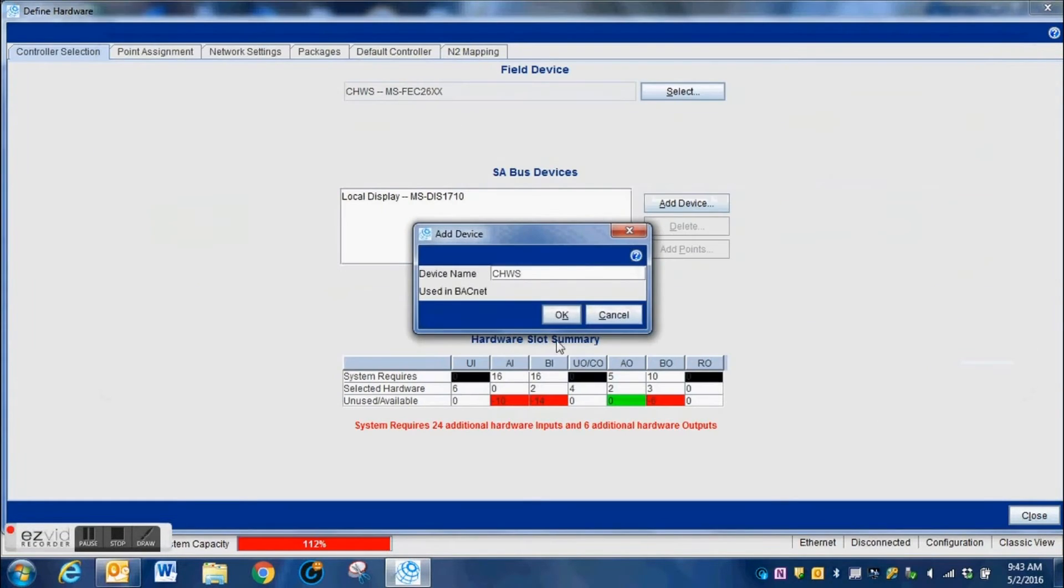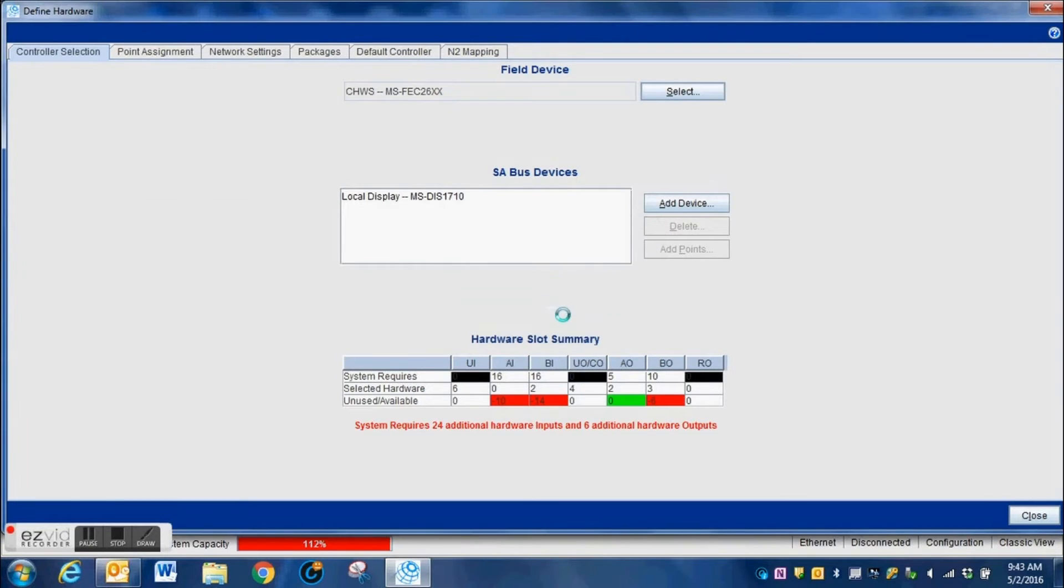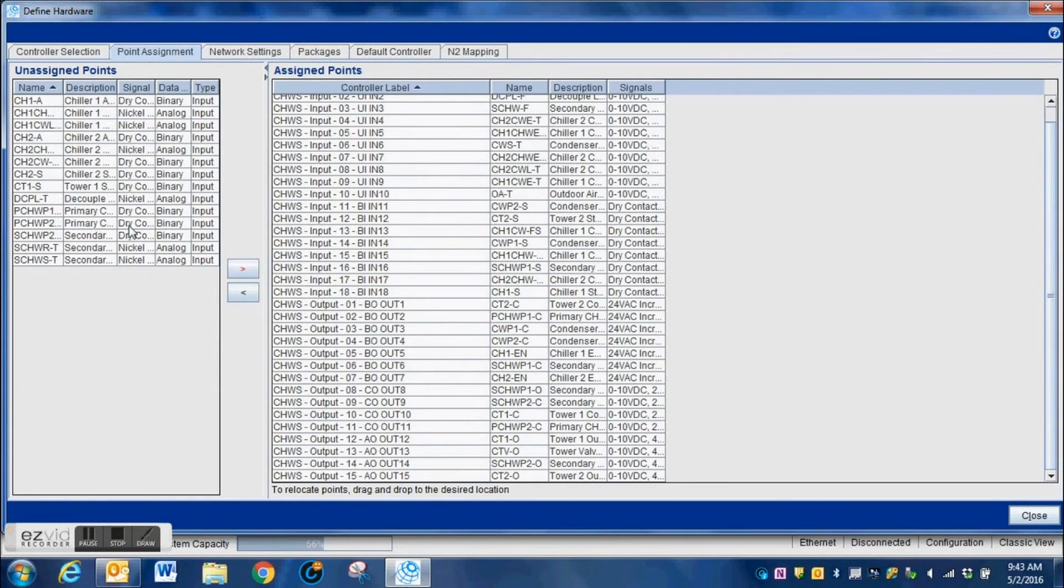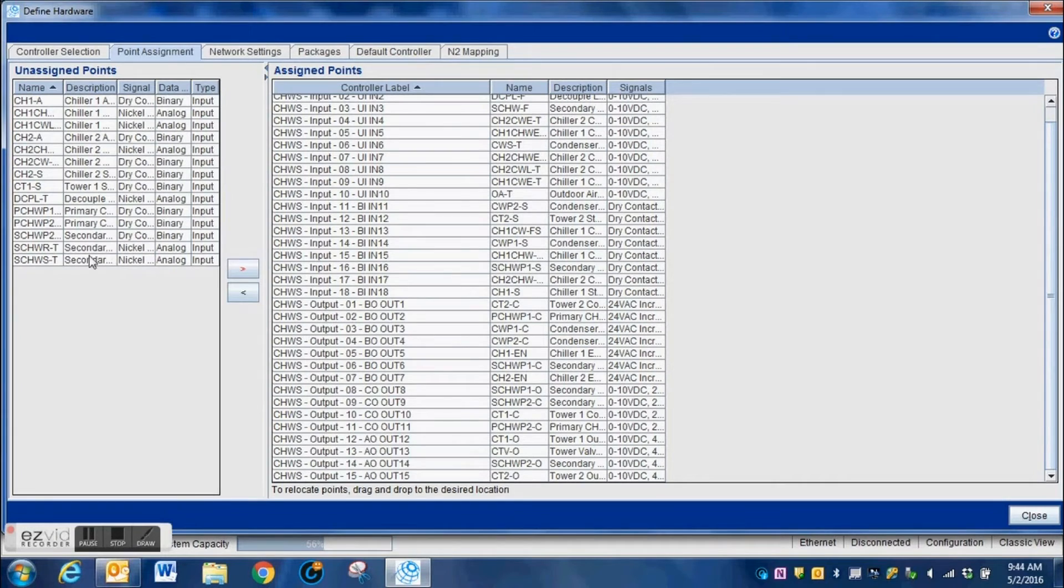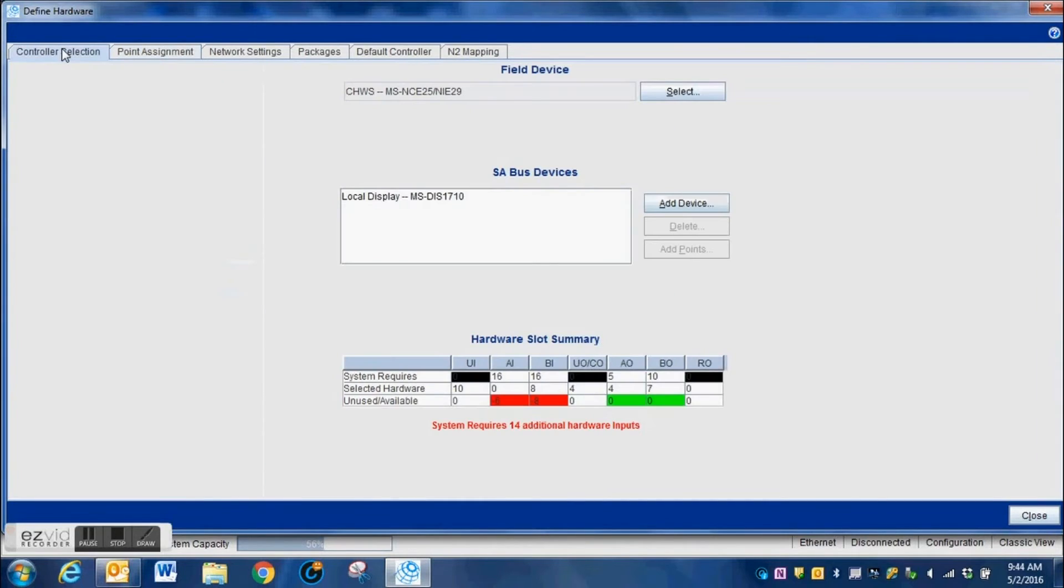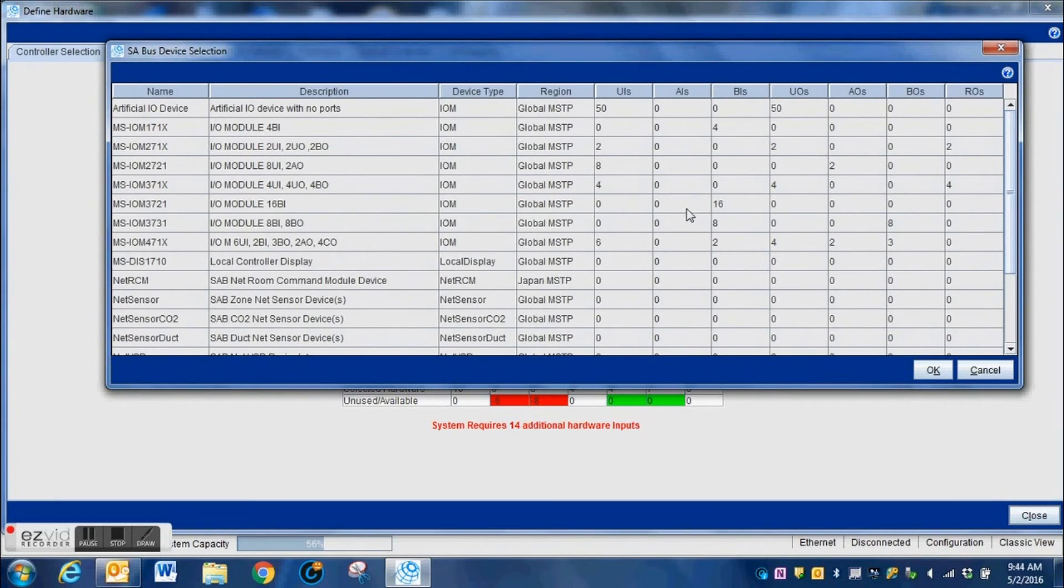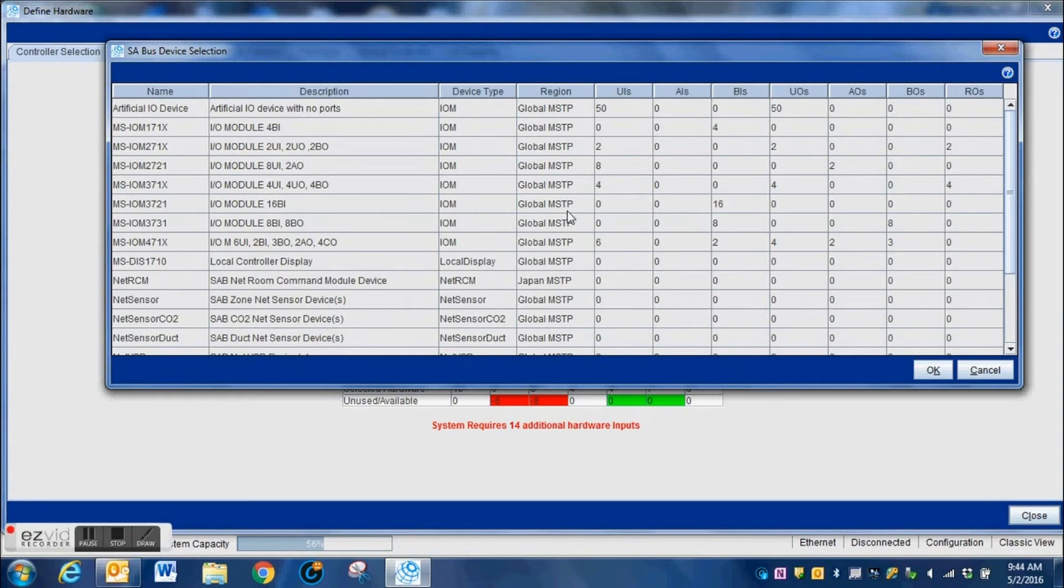The reason is the hardware inputs on one particular controller may not be enough. You may need a few more binary inputs, a few more analog outputs. Every system is a little bit different. You can see here that what we have selected so far, the controller is full, but we still have all of these hardware points that we need to put somewhere. So we've got to add enough of the correct control devices to be able to add each of the hardware points to the system.